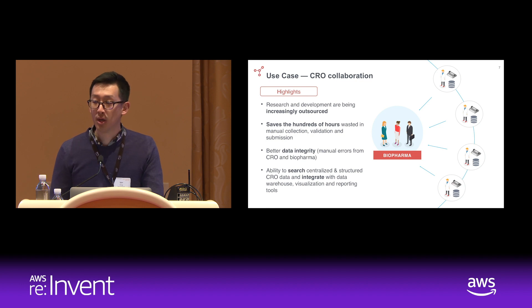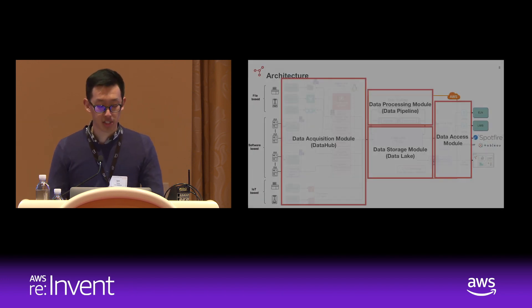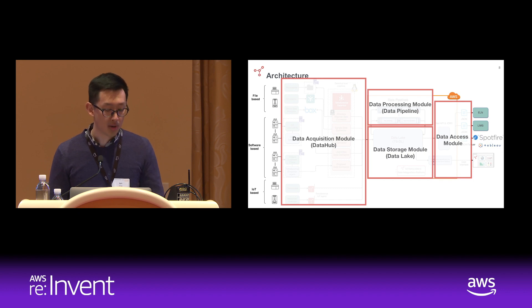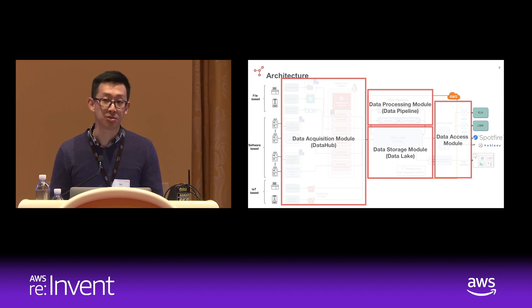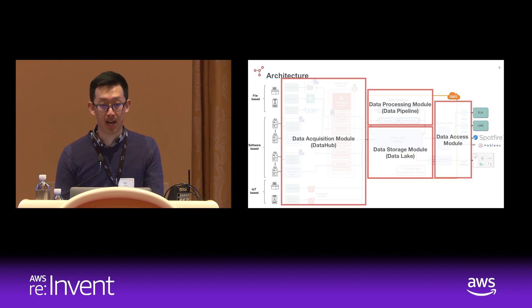Here is the technical architecture. On the left side you have the data source instruments: file-based instruments — or CROs — software-based instruments that don't necessarily produce a file and have some kind of software interface, and instruments like balances and pH meters that don't produce files nor provide an API. This entire architecture has four modules: a data acquisition module, a data storage module, a data processing module, and a data access module.